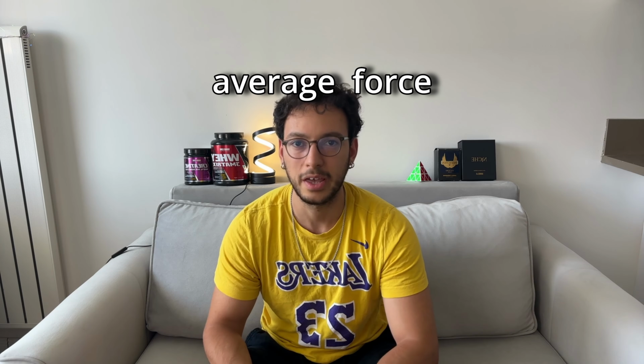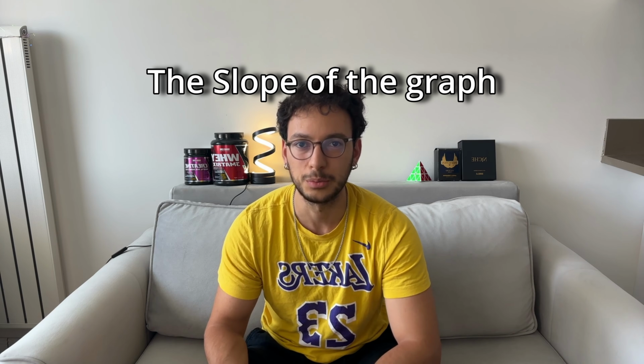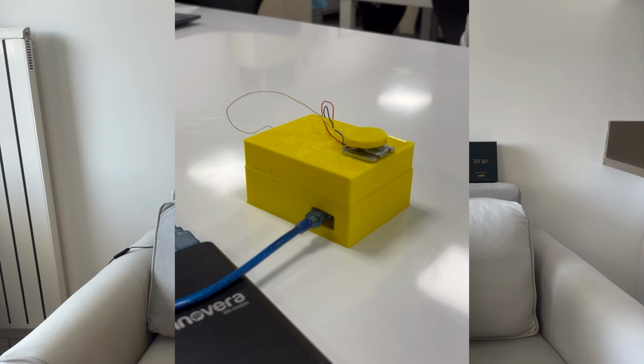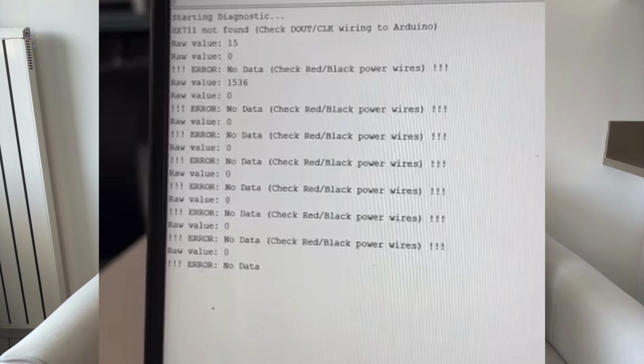Finally, all that was left to do was writing the software. The hardware is only half of it. The software takes a raw force signal and turns it into something clinically useful. The real biomarkers, such as the peak force, average force, area under the curve, the slope. The device moves through defined states, which keeps the readings clean and repeatable, instead of a chaotic stream of numbers. Everything was going great and I was finally finishing my prototype. I even 3D printed a box around it, until this happened.